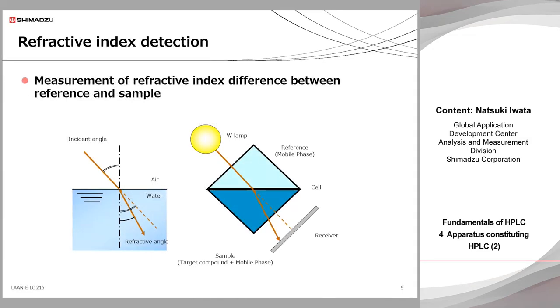A refractive index detector — so-called RID — employs the light refraction phenomenon on a gas-liquid surface. The figure on the right side shows a cross-section of the RID cell that has two separated chambers: one is a reference cell filled with mobile phase, and the other is a sample cell connected to the flow path of HPLC. Before analysis, the reference cell is completely displaced with fresh mobile phase by switching the flow path to the HPLC side, then the flow path is switched back. When the target compound does not exist in the sample cell, both cells are filled with the same mobile phase so that no refraction occurs and the light beam proceeds straightly. When the target compound reaches the sample cell, the light beam is bent due to the change of refractive index, and the RID can detect this change.